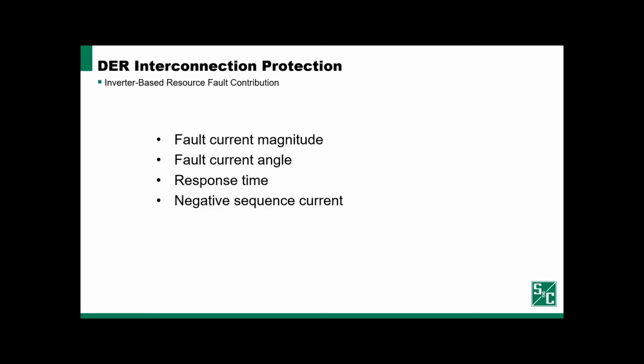Another key characteristic is negative sequence current. Negative sequence current is present in unbalanced faults, and it is something that we very commonly use in our protective devices to identify the presence of a fault, as well as identify the location of that fault. Conventional rotating machines, of course, produce negative sequence current in response to unbalanced faults, like a phase to earth fault or a phase to phase fault.